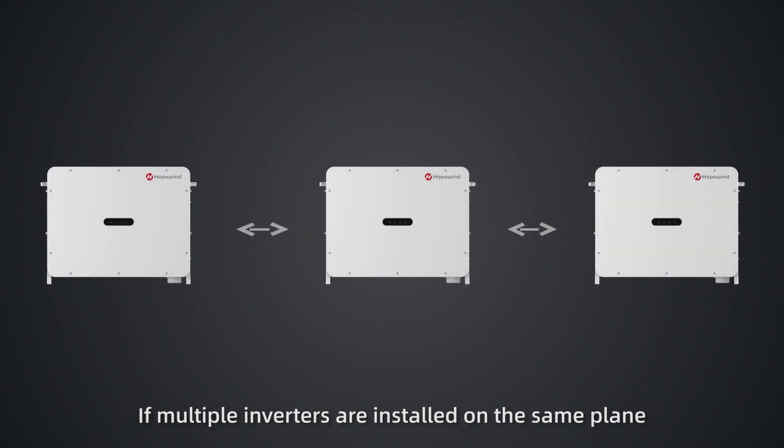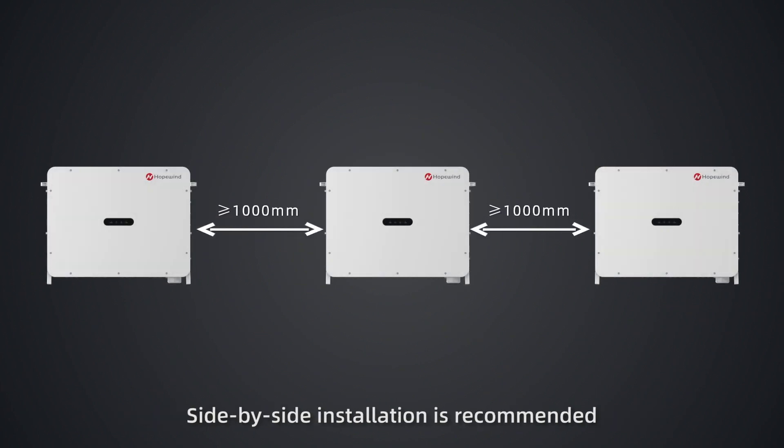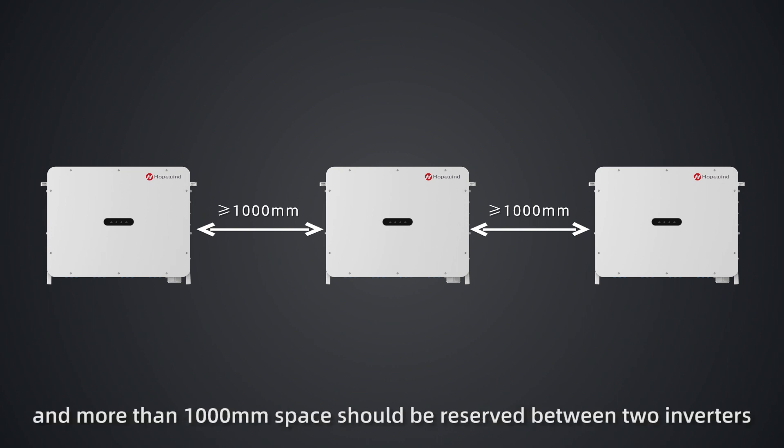If multiple inverters are installed on the same plane, side-by-side installation is recommended, and more than 1000mm space should be reserved between two inverters.